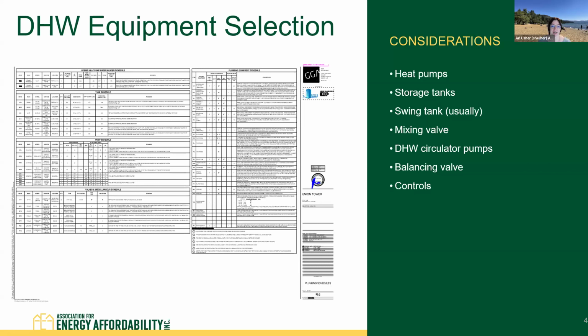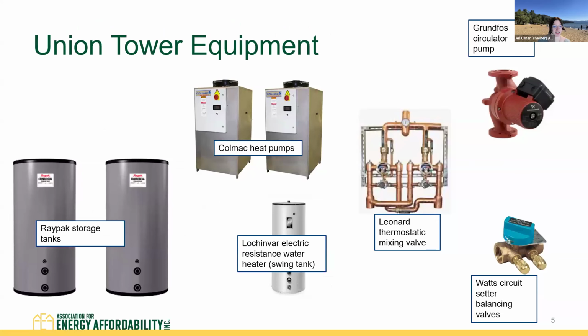But in a central system, you've got a plant that is made up of a handful of components. Those components are typically your heat pumps themselves, which heat up the water, and your storage tanks. You usually have a swing tank and a mixing valve. And then for distribution, you've got circulator pumps, balancing valves, and controls to control everything. So here's the equipment that we have on Union Tower. How does it all fit together, though? What we like to do at AEA is an exercise that I'm going to call the water molecule journey. On the next slide, we're going to imagine ourselves as a single molecule of water and figure out how we're going to move through the water heater plant.